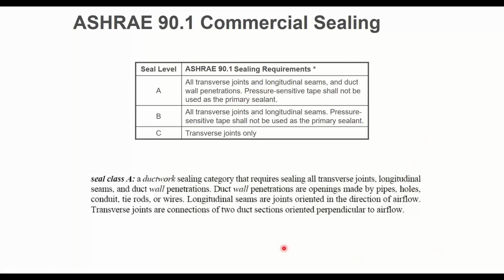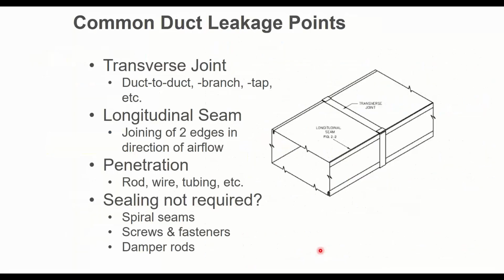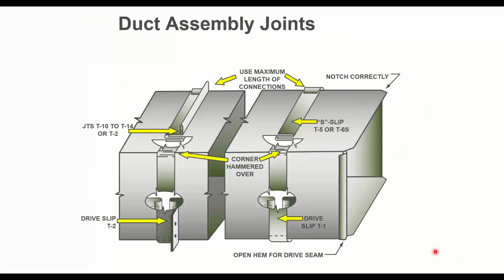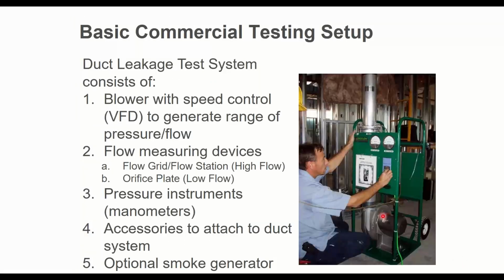Still got to seal it. Exhaust duct, still got to seal it. You got to seal everything at this point. And by the way, for the guys who do residential, it's the same deal. You got to seal all your duct work now. There's no duct work in any space that no longer has to be sealed by codes. Once again, though, existing buildings, you got plenty of unsealed duct work out there. Most buildings. We keep moving here just in the interest of time. I'll skip that. All right.